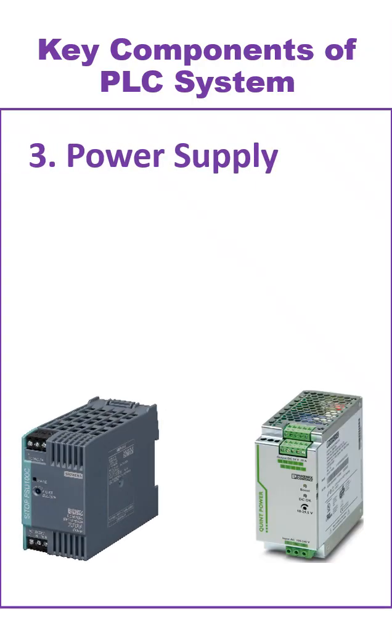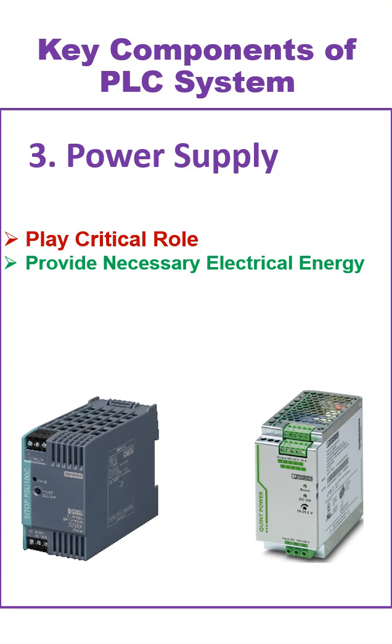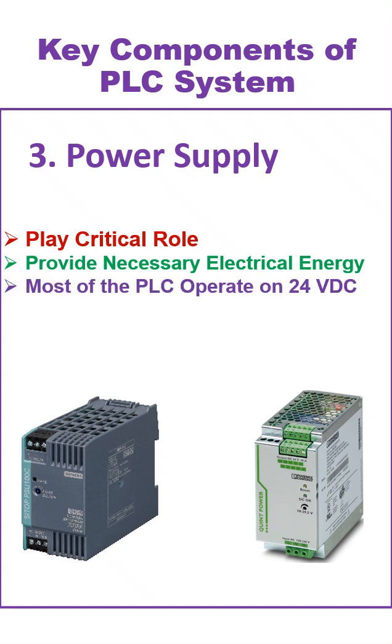The power supply in a PLC system plays a critical role in ensuring the reliable operation of the entire system. It provides the necessary electrical energy to the PLC CPU, I/O Modules, Communication Modules, and other connected peripherals. Most PLCs operate on 24V DC. The power supply unit converts AC power to the required level of DC power.